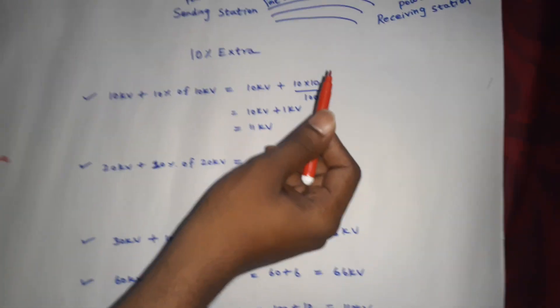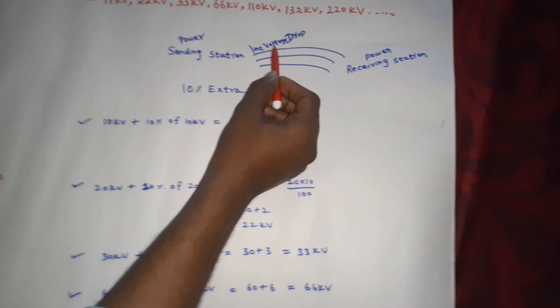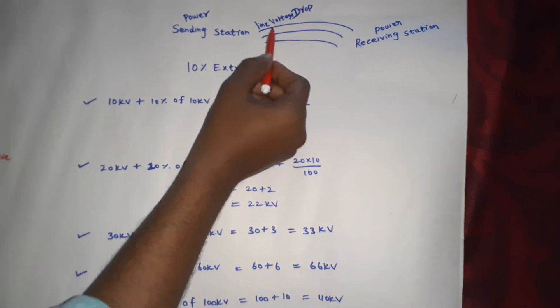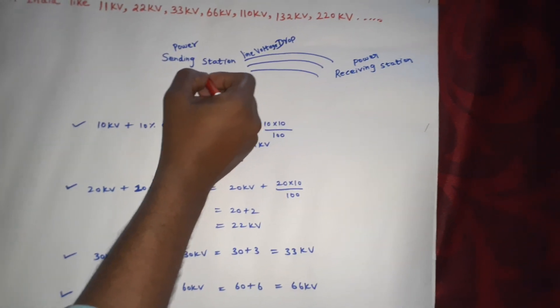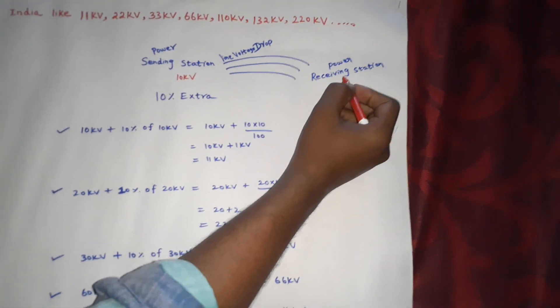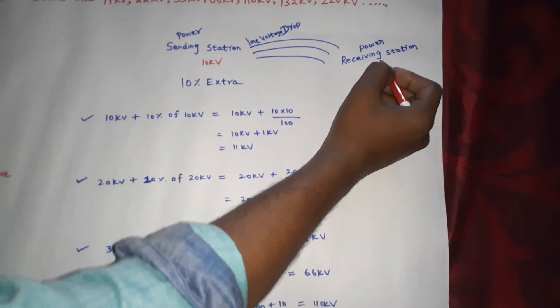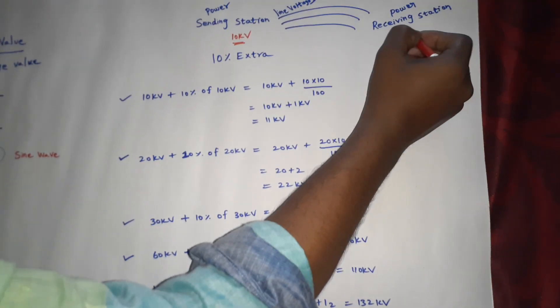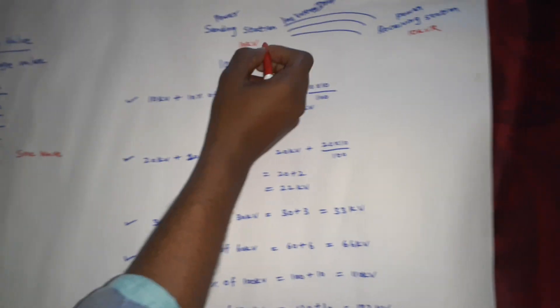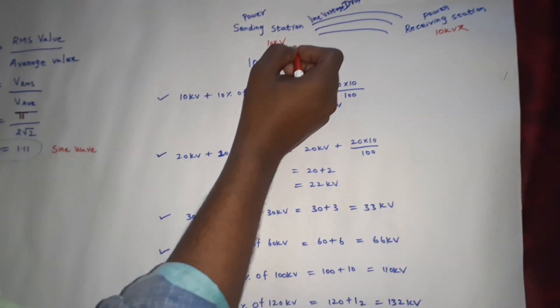If you use aluminum conductor, you will have a loss, that is called I²R loss. There is a line voltage drop due to its impedance or inherent resistance. Suppose if you transmit 10kV, you cannot receive the full 10kV. That is a loss. What is the loss? 10kV minus 10% equals the received voltage.